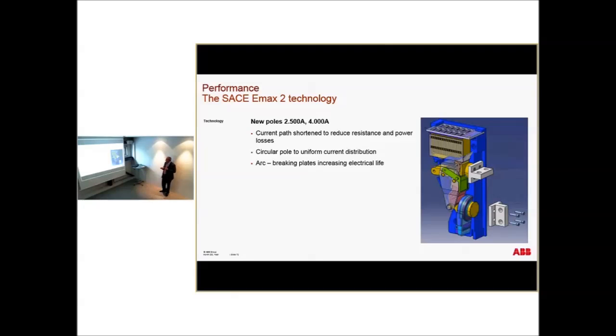The breaking plates increase the electrical life, so we redesigned. It's far more expensive. It costs twice now. The arcing plates, we changed the material, and this is the real heart of the breaker. It's not the electronics. Everything is done outside of this breaker. We assemble, in particular, accessories. This part here is only made inside the factory. It's like the Coca-Cola recipe. It's very important to find the right material to make this interruption. Looks stupid, but so again, we redesigned totally the arcing chambers.